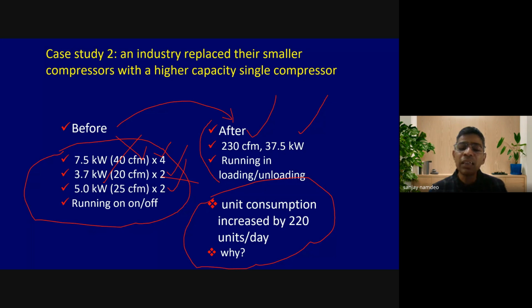Nothing wrong with the technology, but something went wrong which led to this increased power consumption, and that was the incorrect size of the new compressor. By just adding the capacities of the old compressors, they added some margin and bought a new compressor of higher capacity, 230 CFM. When a higher capacity compressor runs for a lower load or a lower requirement, it will run in loading and unloading mode. During unloading, it does not generate any compressed air, but it consumes unloading power. It means this bigger compressor was not compatible with their current requirement or the current flow. So nothing wrong with the technology, but there was a wrong selection in terms of the capacity of the new compressor. That led to the higher energy consumption.